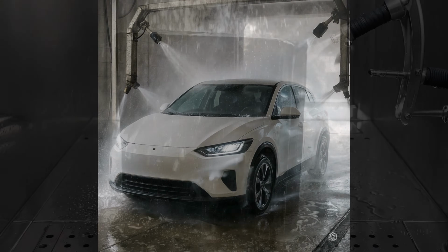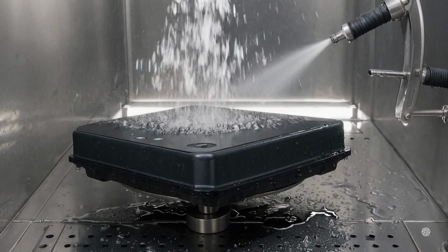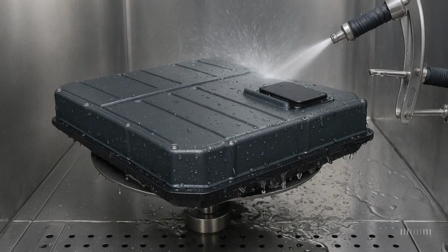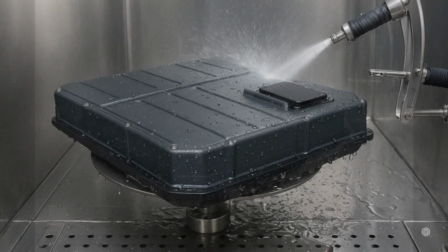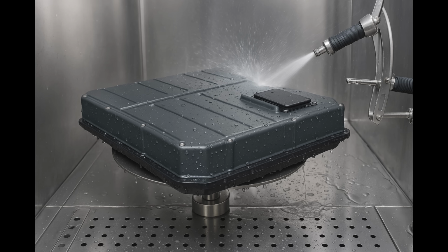The 9K in IP69K means protection against high pressure, high temperature water spray. Test conditions include water pressure at 80 to 100 bar or 1200 to 1450 psi, water temperatures at 80 degrees C, a flow rate of 14 to 16 liters per minute. Distance from nozzle is typically 10 to 15 centimeters, and spray angles include 0 degrees, 30 degrees, 60 degrees, and 90 degrees. Spray durations are often 30 seconds per angle, often with the device rotating on a turntable. This test is often repeated multiple cycles to simulate repeated washdowns or splash exposures.